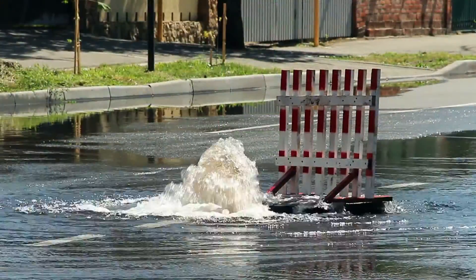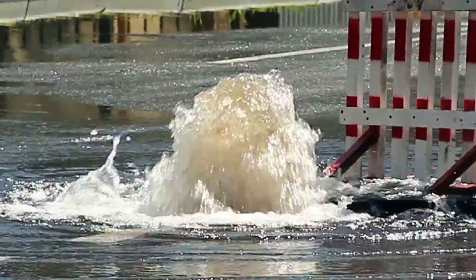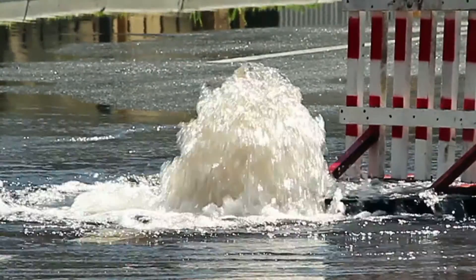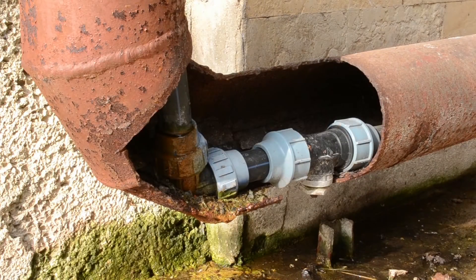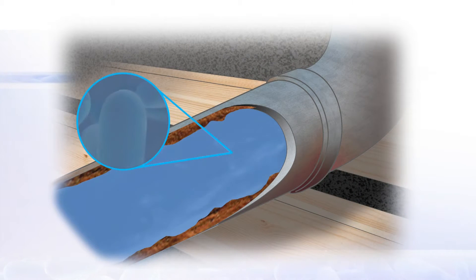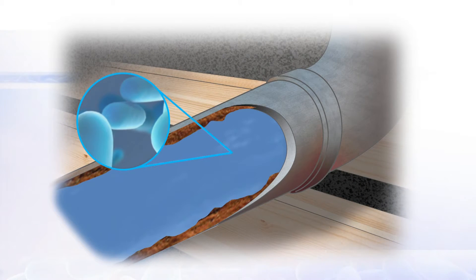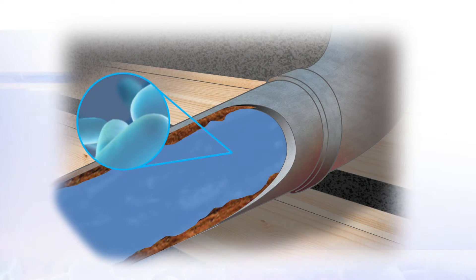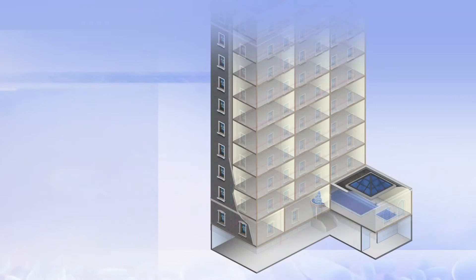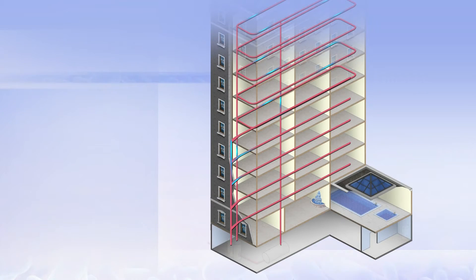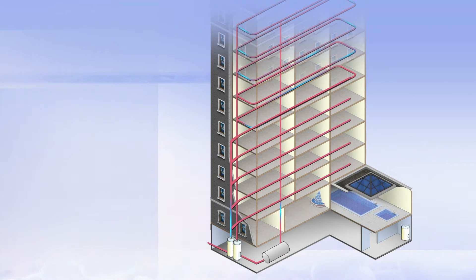It's also important to know whether there have been any water disruptions because Legionella can be introduced during water disruptions, and pressure drops in the premise plumbing system can release Legionella from the biofilm. The premise plumbing in a building includes all the pipes, devices like water heaters, and fixtures like faucets that bring the water to the user.